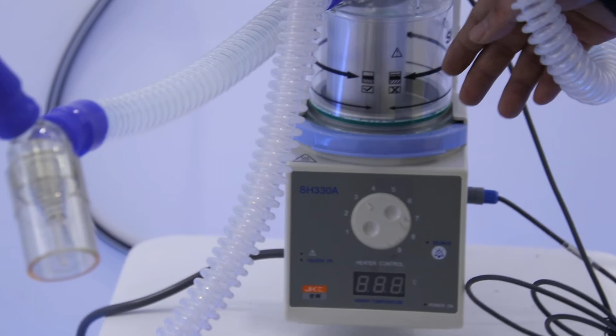And this one is the humidifier. For the humidifier we have a total of 3 types, and this one is the digital one. You can see here is the water trap, and this one is the foundation. And we can use our finger very easily to change the temperature to different levels, and the temperature will be shown here in real time. For the pipeline here, all the pipelines we are using, no matter for adult or children or neonatal, are the reusable ones. So usually you can use it for a long time. Usually it can be used for 3 to 4 months.